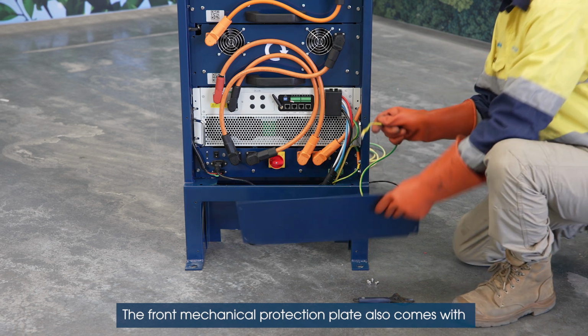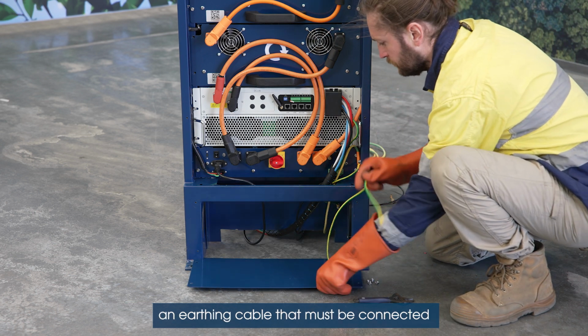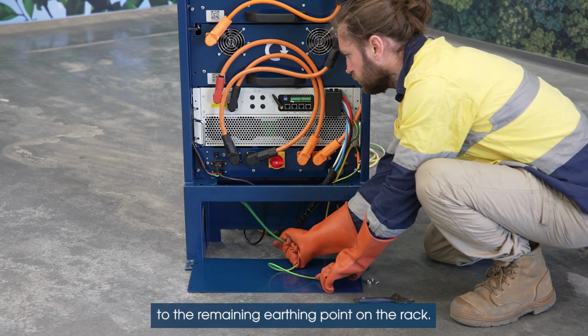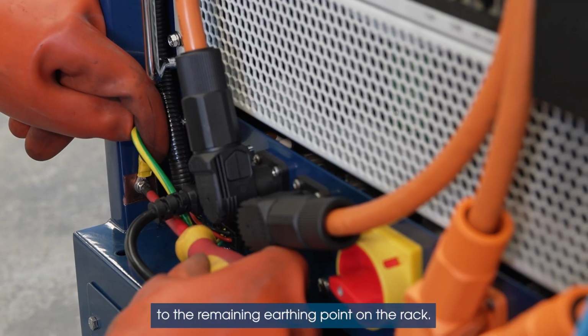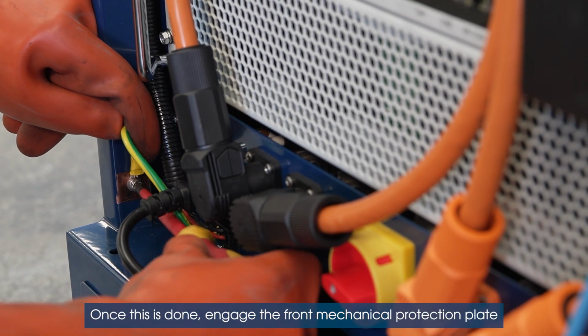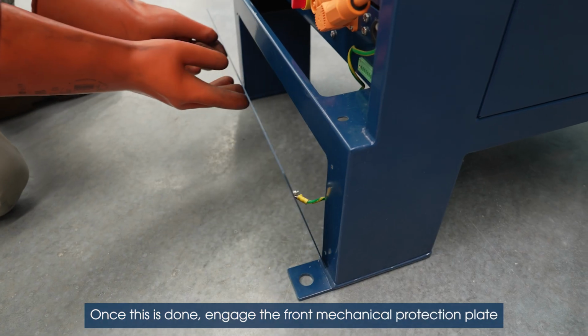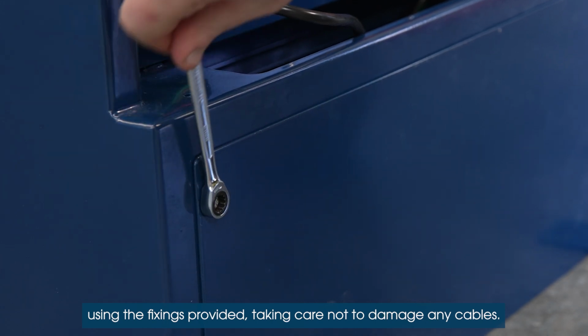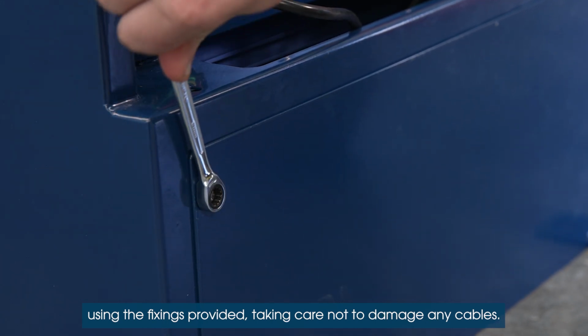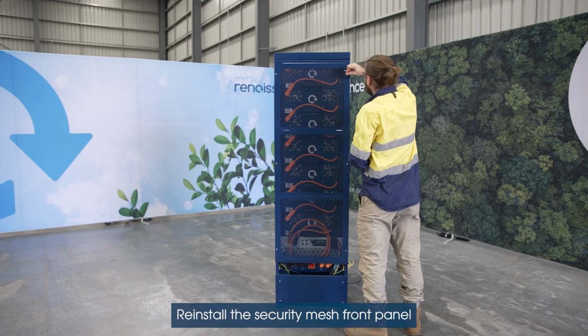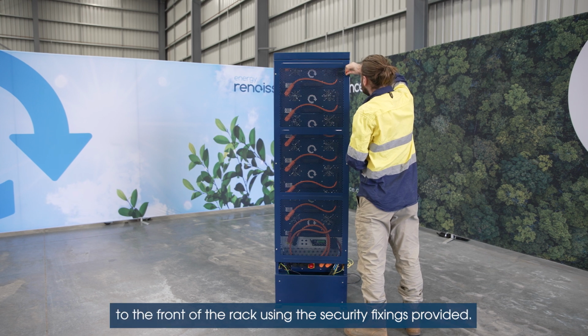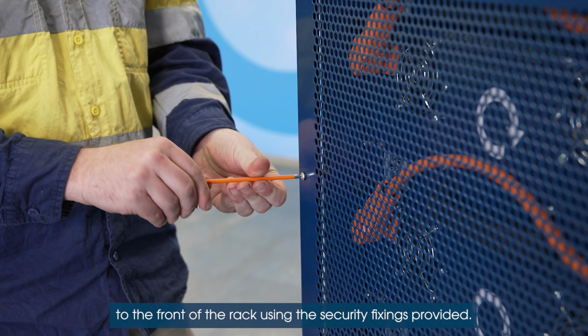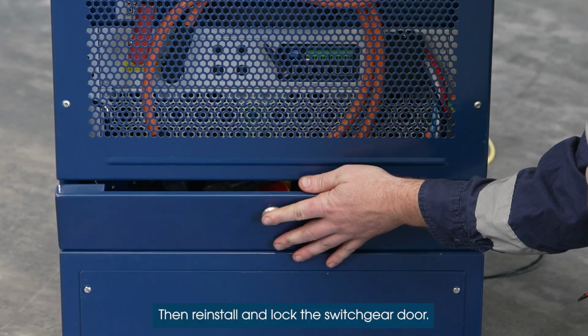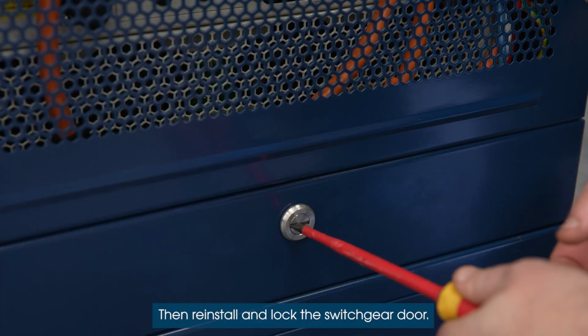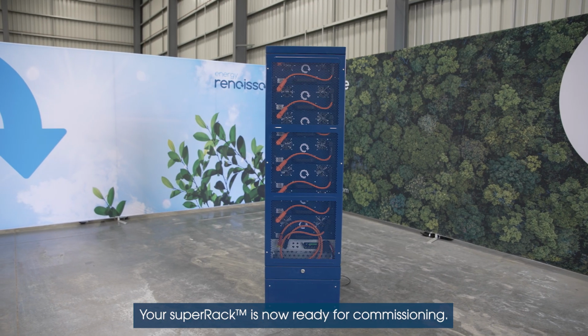The front mechanical protection plate also comes with an earthing cable that must be connected to the remaining earthing point on the rack. Once this is done, engage the front mechanical protection plate using the fixings provided, taking care not to damage any cables. Reinstall the security mesh front panel to the front of the rack using the security fixings provided. Then reinstall and lock the switchgear door. Your superRack is now ready for commissioning.